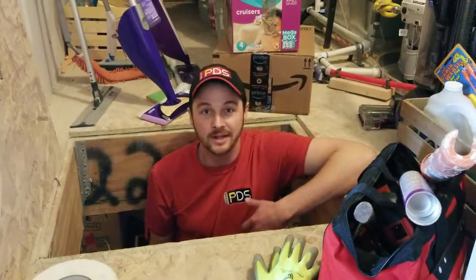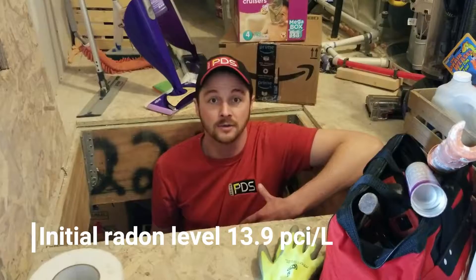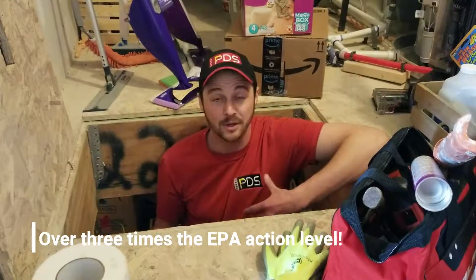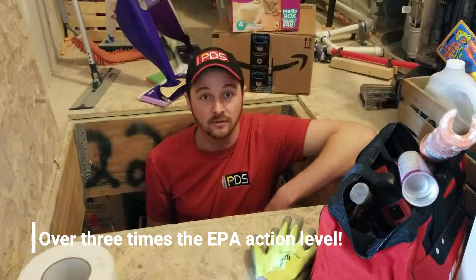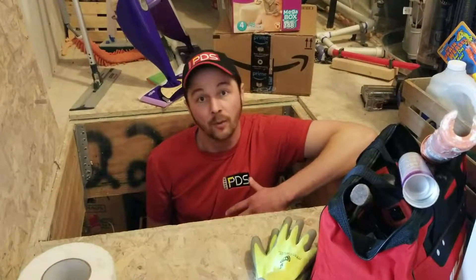Hi, this is Brent at PDS. We're here at the home of one of our good friends. They just purchased a brand new home and the builder told them there was a passive radon system in the house. We're going to go down and inspect it and see what needs to be done to activate the system, since their short-term test results came back at 13.9 picocuries per liter — nearly four times the EPA recommended action level of four picocuries per liter. So quite dangerous radon levels in this home.